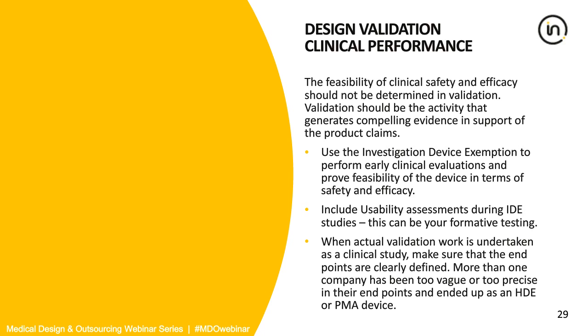The FDA does differentiate between significant risk devices and non-significant risk devices during your IDE, so you'll have to keep all that in mind. If you are doing early IDE work or throughout your clinical evaluation, you do want to do usability assessments. If you're doing it early, like your first time, an alpha prototype into a clinical evaluation under an IDE study, this could be your early formative testing where you're collecting information about the user interface. And then later on, when you go in for your final clinical testing to verify that the product meets all the requirements and the user needs, then that would be your summative testing.